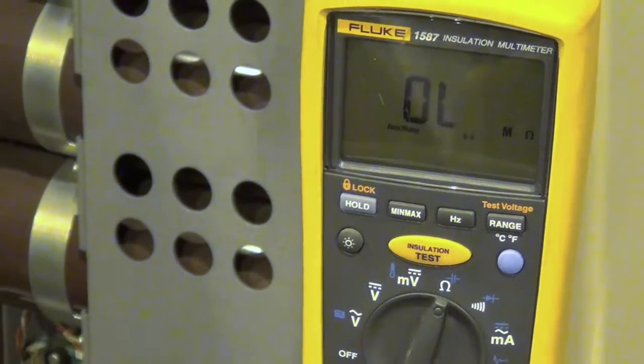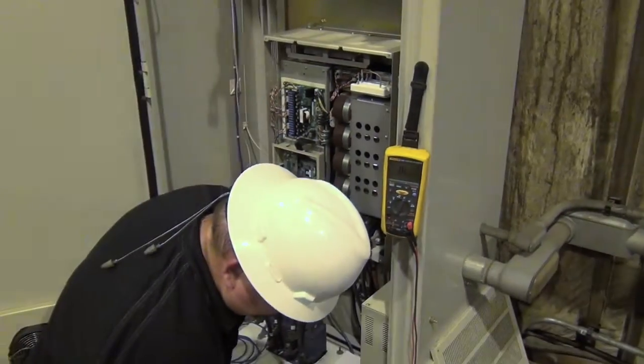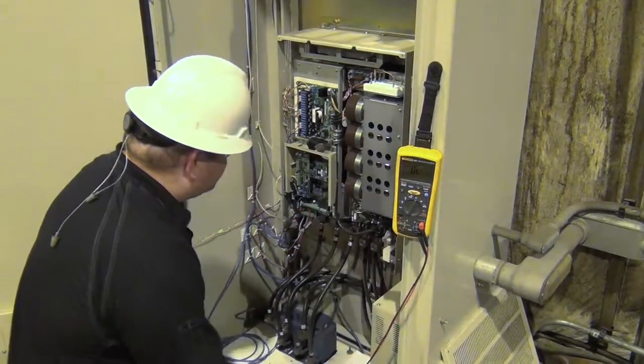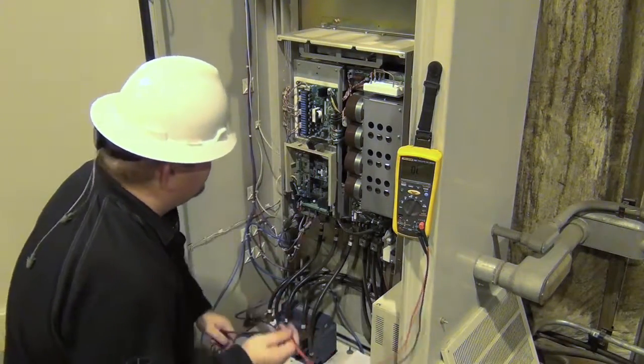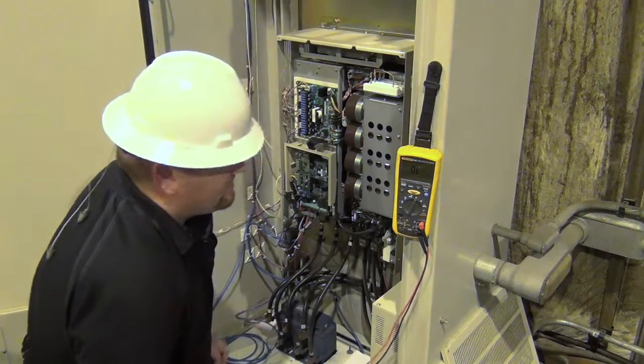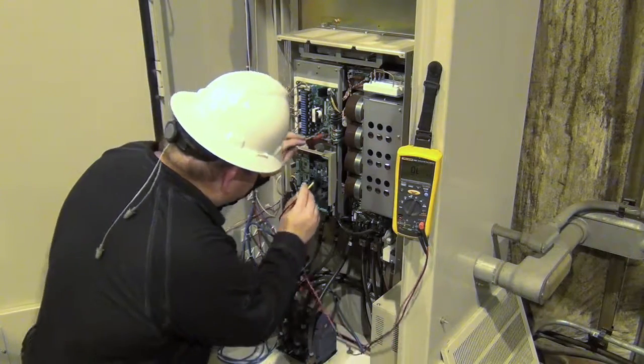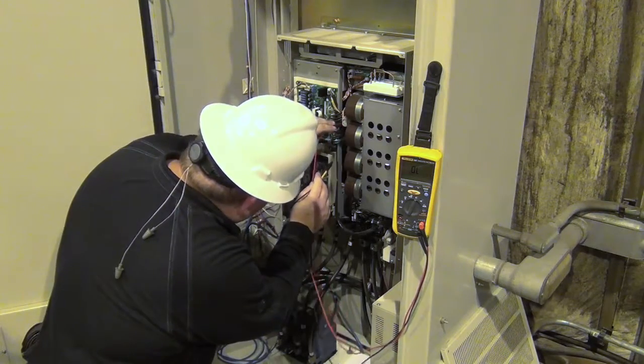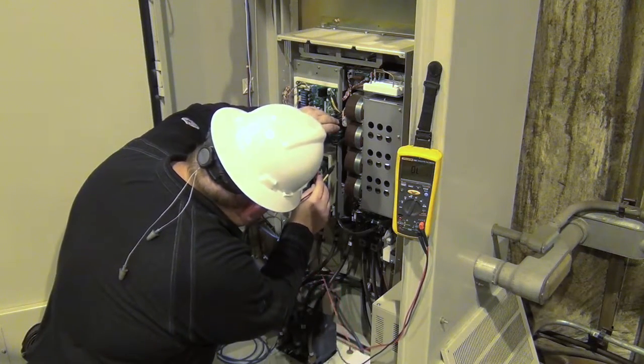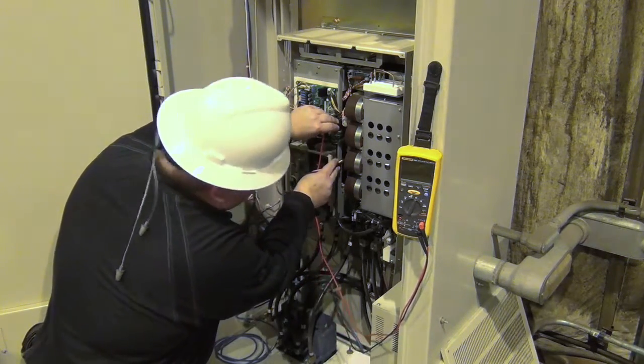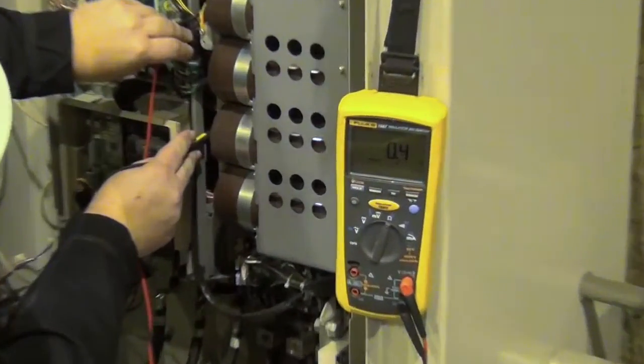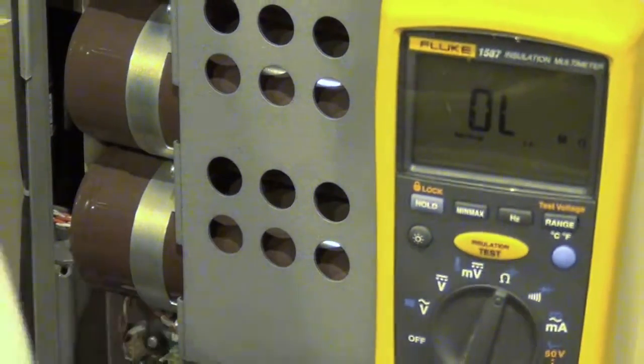What you're looking for is to make sure that obviously it's not shorted. So this particular drive actually does have a DC bus fuse present. So what we'll do is take our probes, come back in and get on that guy, top and bottom, and verify at 0.5 so that fuse is still good.